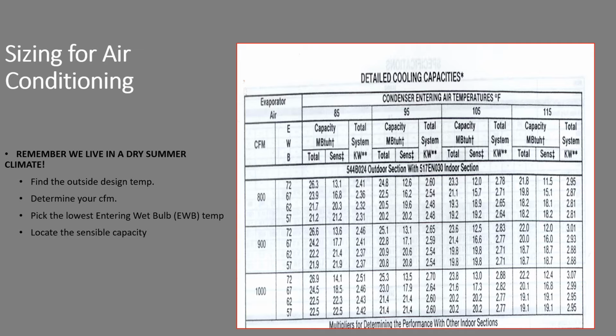You find the outdoor design temperature. In this case, it's up here near the top. You determine your CFM, and this happens to be for a 2-ton system. You start at 800, you go to 900, you go to 1,000. Please notice it doesn't go down to 700 or 600. So again, these charts are only valid if you have perfect airflow and perfect charge. You pick the lowest entering wet bulb, 62 or 57 degrees is safe. Remember, it's going to be hot. The air conditioner is going to be running for a long time, and the air will get dried out the longer that air conditioner runs.